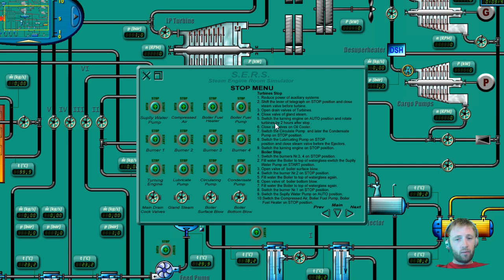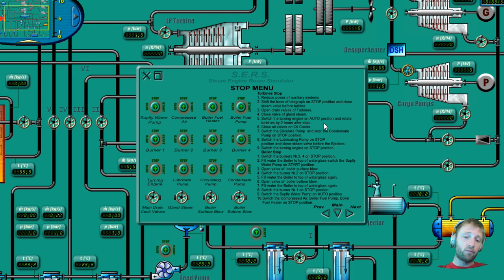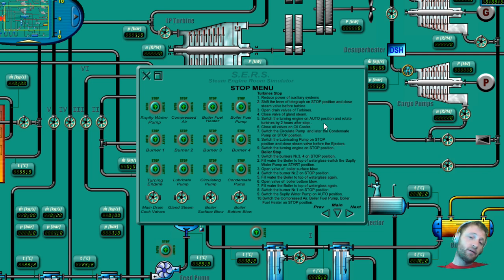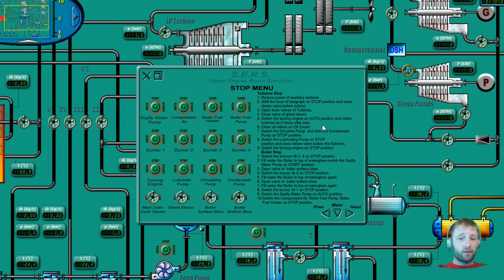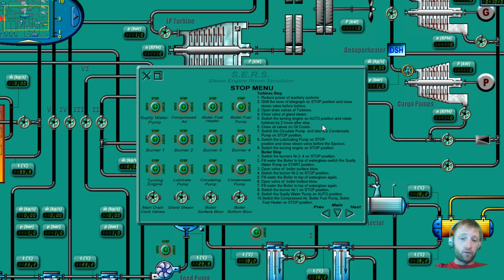What else? Switch the turning gear on auto position and rotate turbines by two hours after stop. Check how much time it needs to turn after stop, because these are big turbines. There are a lot of parts included and the turning is necessary to remove all the moisture inside the turbine.